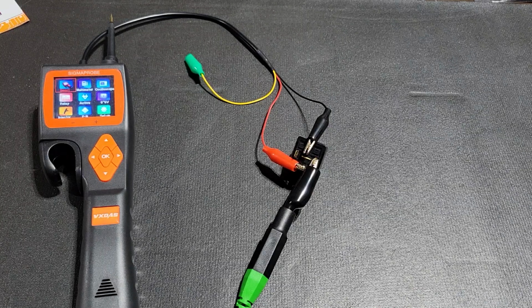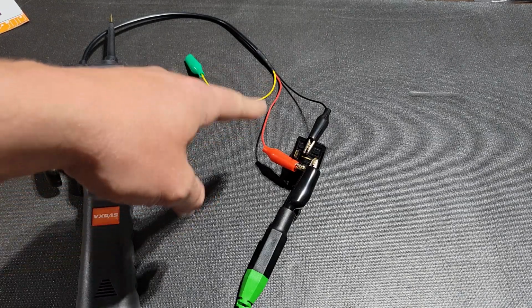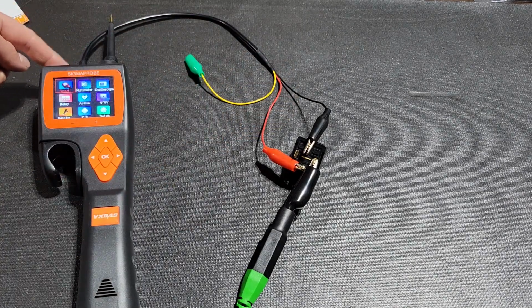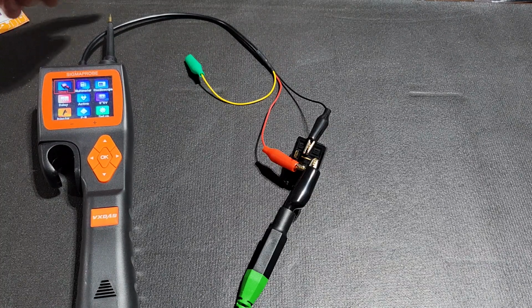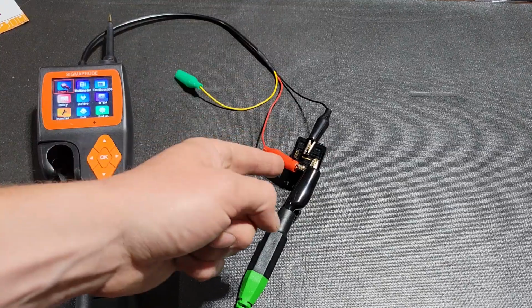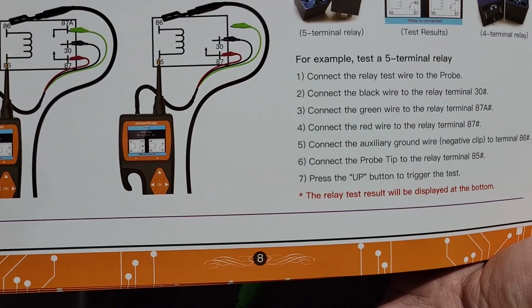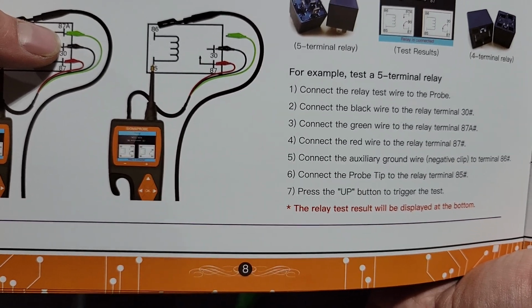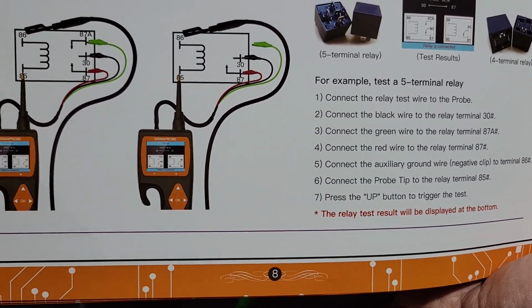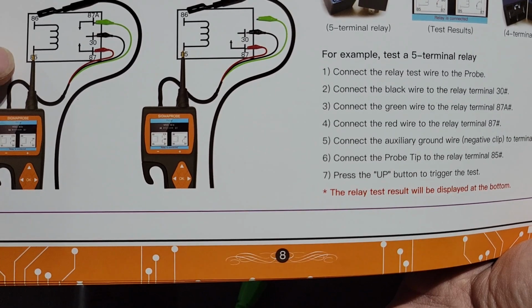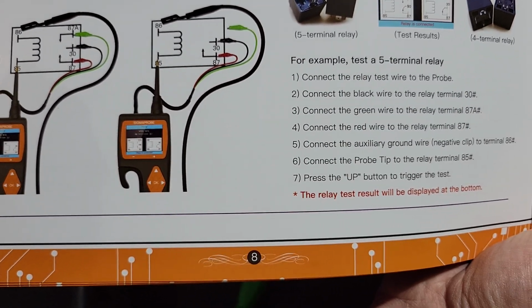Here we have it connected to the relay. I've taken the relay dongle and attached the aux portion up here at the top of the unit. For a 5-post relay you will be using the green, but for this 4-post we will not. The green will go to the 87 alpha, but we don't have an 87 alpha since this is a 4-post relay, so we're going to disregard the green.